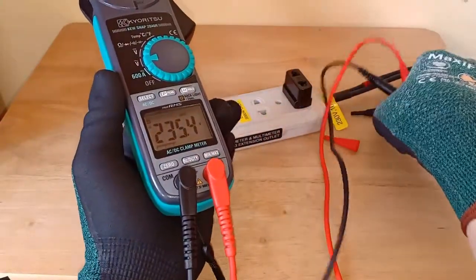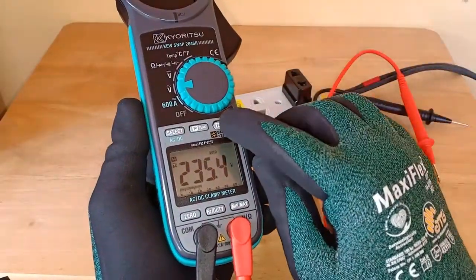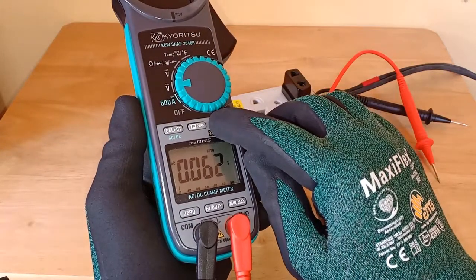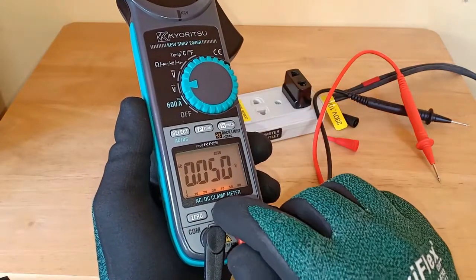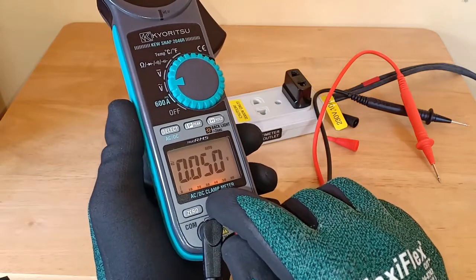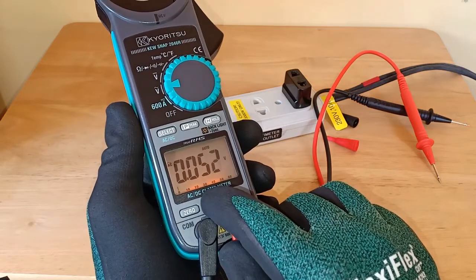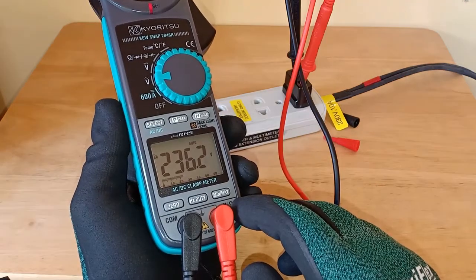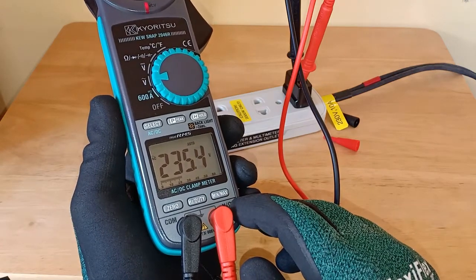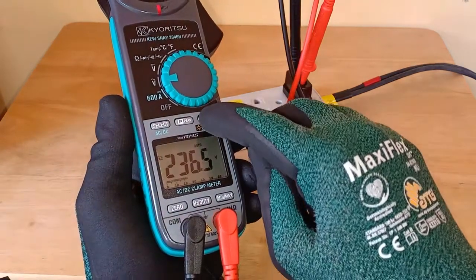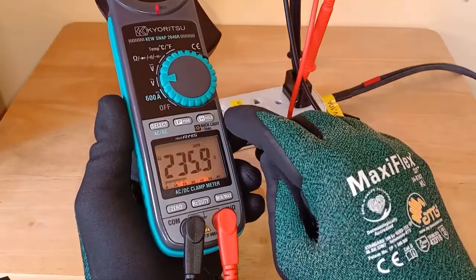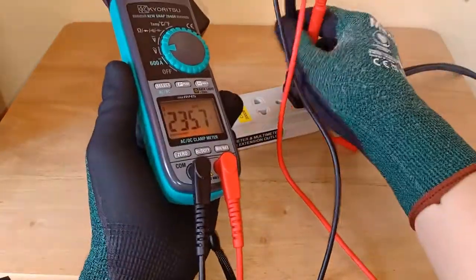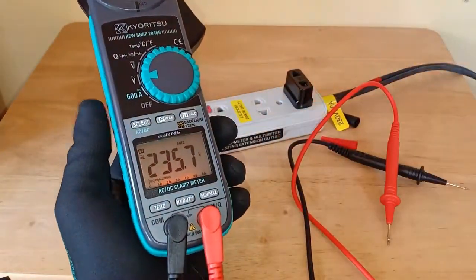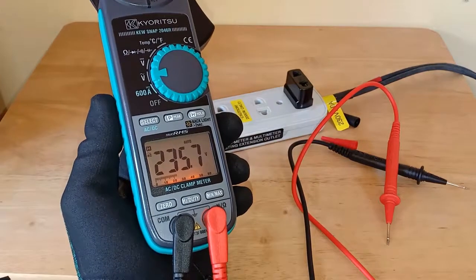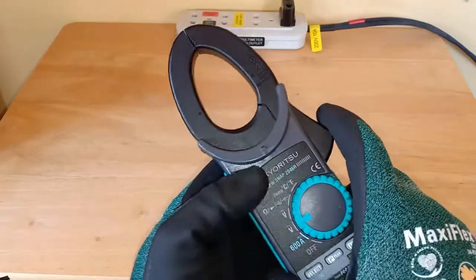and remove the test leads at the test points and turn on the backlight, the frozen value will disappear. The instrument will disengage the hold function. If you want to enable backlight at the same time hold the value on screen, first turn the backlight on and hold it, and then you have the value with the backlight on. The clamp meter's jaws are operated using this lever.